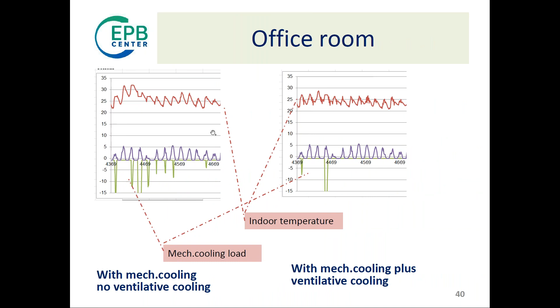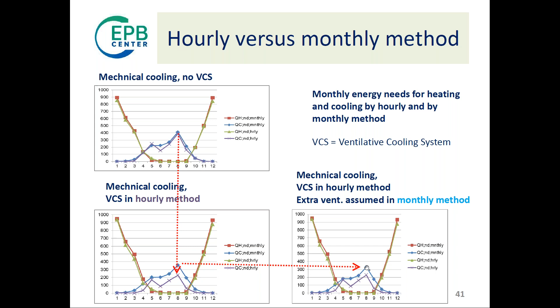Here you see the monthly values for the hourly and the monthly method from the ISO 52016, shown from the spreadsheet. Without ventilative cooling system here, and then the hourly method with ventilative cooling system, so the cooling needs have dropped. Now you try to do the same for the monthly method, but as I said, you have to use trial and error to find the correct match with the hourly method. So here the match was not found yet.